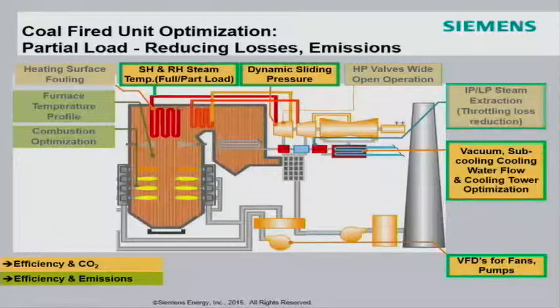And one of them is the energy of the condensate and feedwater systems. We can actually utilize those sources of energy to bridge the delays in the coal firing. The firing delays, everybody knows that in coal, are much longer than in gas, for example. So while you're bridging those delays for faster load ramps and maneuverability, you utilize the energy storage to do that.